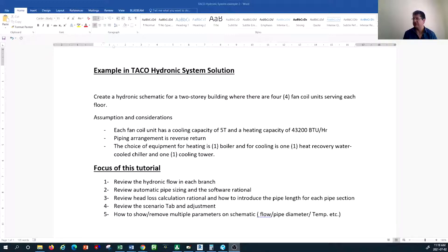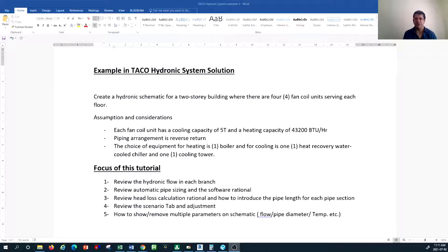In this tutorial we're going to create a hydronic schematic design. We assume this is a two-story building and we have four fan coil units on each floor, for a total of eight fan coil units. All fan coil units have the same cooling capacity of five tons and a heating capacity of 43,200 BTU per hour. The piping arrangement we are going to select is reverse return.